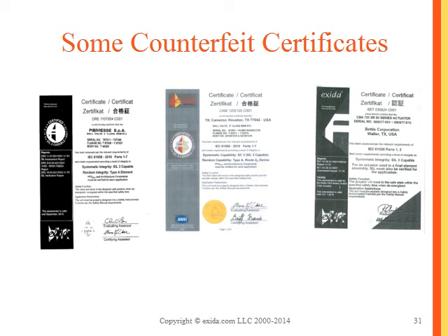I don't know. But these certificates, these counterfeits, have been found on the market, and I'm just posting them here as an example. But how, as an end user, do you know that this certificate is valid or is not valid? The newer ones, this one here even has the ANSI logo. Of course, the Photoshop capabilities of people tend to increase. They look pretty good, and I recognize some signatures. So obviously they had a copy of a real certificate, and they were just making changes to them.